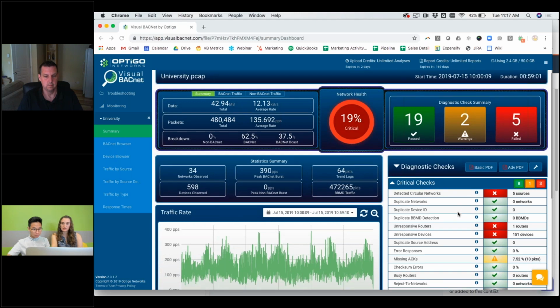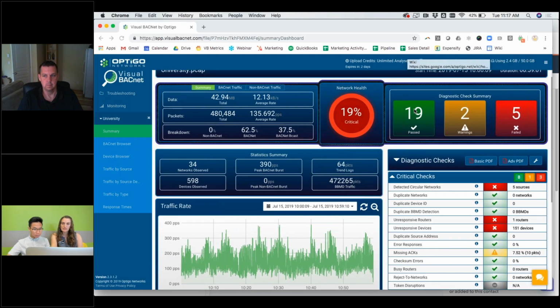Okay, so if a device ID comes up but it's not installed in the field, what's the issue? It's likely because a device is looking for that device ID. So it's saying, who is device 2475128? You need to go to the source, the querying device that's sending that packet, and ask why it is looking for that device. It might be factory reset, or sometimes it's about legacy stuff in the programming.